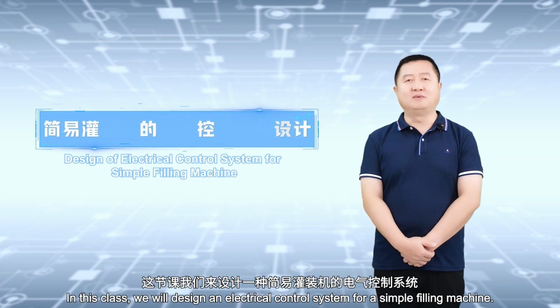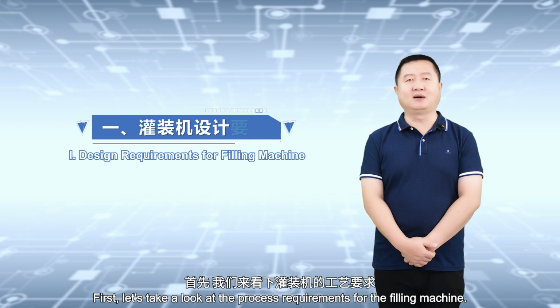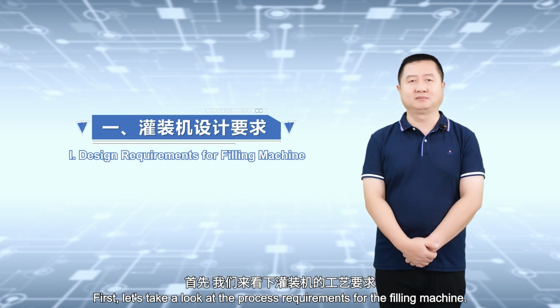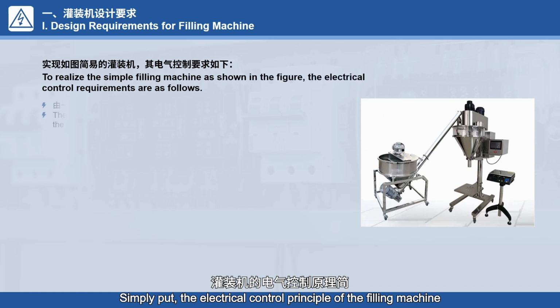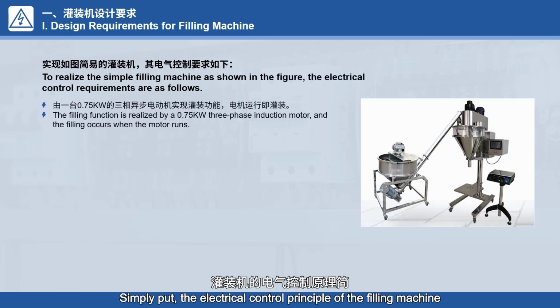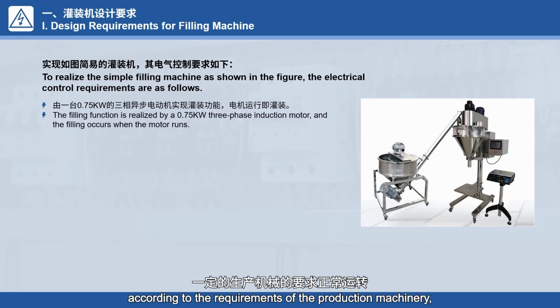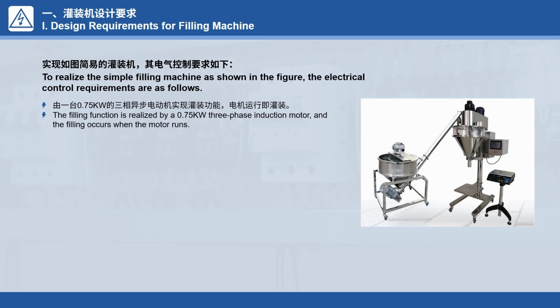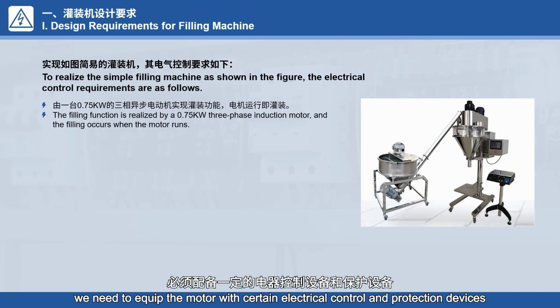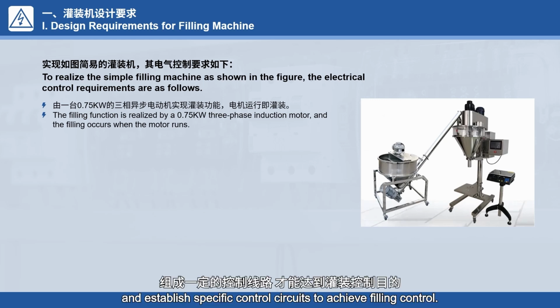In this class, we will design an electrical control system for a simple filling machine. First, let's take a look at the process requirements for the filling machine. Simply put, the electrical control principle of the filling machine comes down to the control of the motor. To ensure that the motor operates normally according to the requirements of the production machinery, we need to equip the motor with certain electrical control and protection devices and establish specific control circuits to achieve filling control.